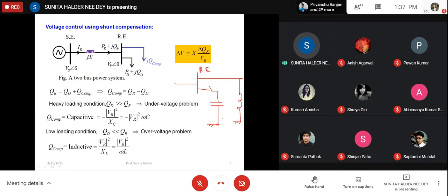Now there are so many such devices in the present power system. I shall discuss only two of them. And this does not mean that the application of capacitors and inductors is obsolete now - obviously they are still there, because direct application of capacitors and inductors has some advantages. They have no complication in operation - you just connect or disconnect, and if you are sure what the load will be in the next operating time slot, heavy loading or low loading, then you can confidently connect a capacitor or inductor. So both these conventional compensating devices, capacitor and inductor, are still in use. Along with that, there are some advanced devices which can serve as a capacitor or as an inductor, depending on the operating condition.